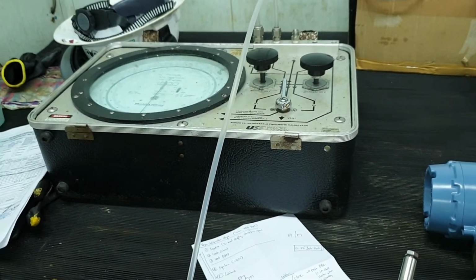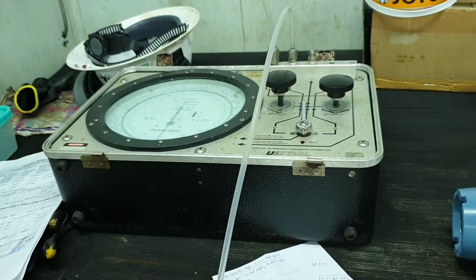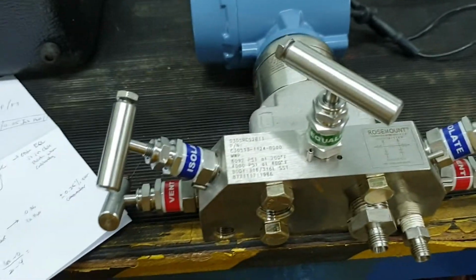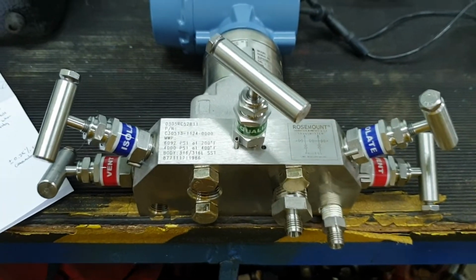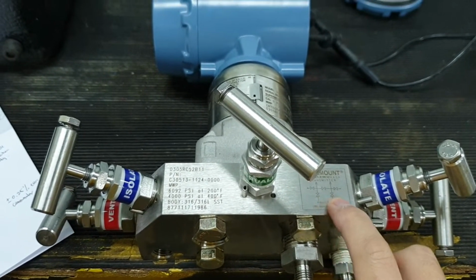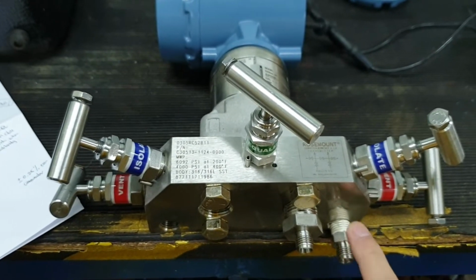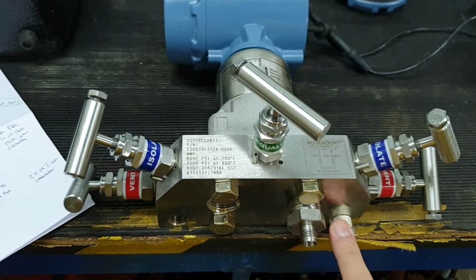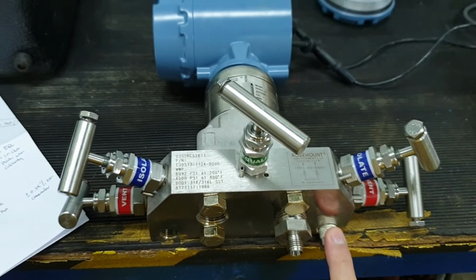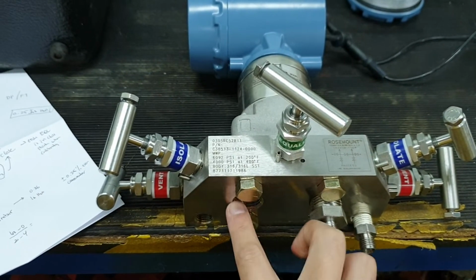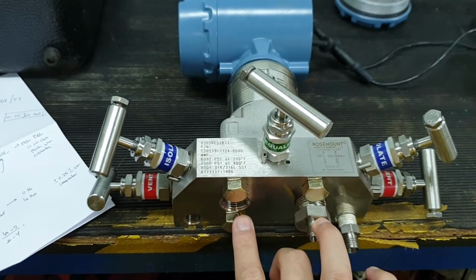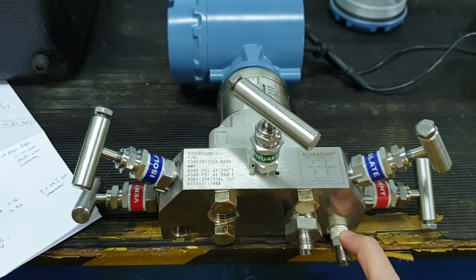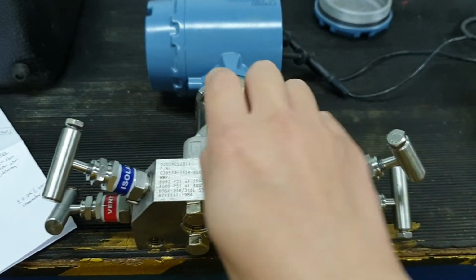Alright, now we're going to connect this calibrator instrument to get pressure to our transmitter unit. But take note that we can connect it either through the main process line or the vent line. For this case, we are going to inject at the vent side. Just imagine that we have a process line and this isolate line. So we are going to inject through this vent line. To do that, we have to first open the equalize valve, fully open.